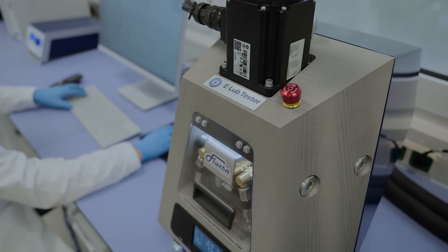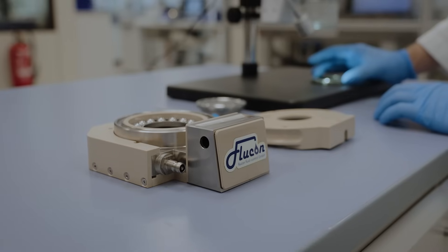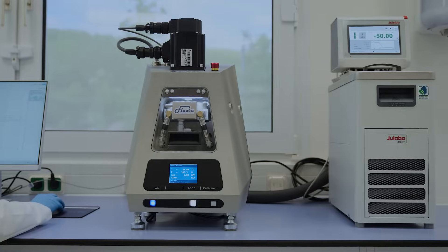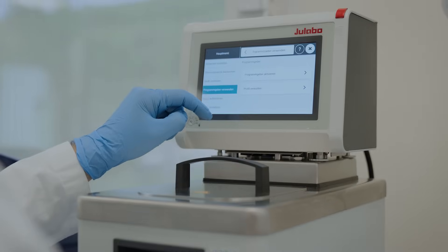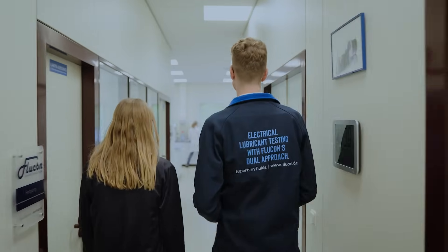Unlike the Epsilon Plus, which operates under constant conditions, the ELUB tester involves moving parts. It includes a ball bearing filled with oil or grease, which is then dielectrically analyzed depending on variables like rotational speed, axial load, and oil temperature. With the Magio series, we especially appreciate the pump system — it has a strong flow rate, ensures rapid heat removal, which is important due to compression heat generated in the lubrication gap.